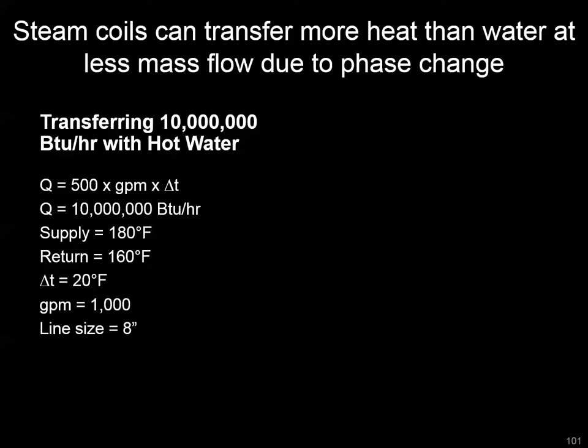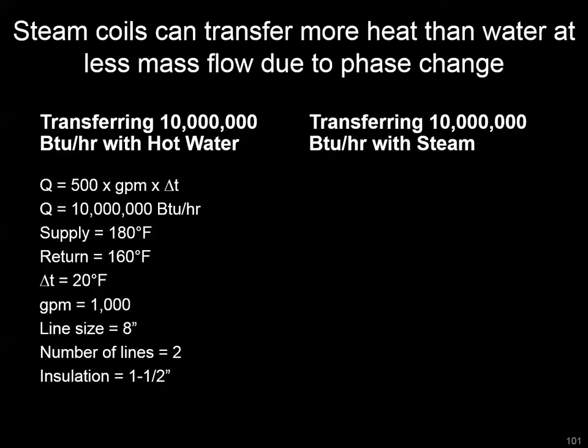For that hot water system we'd probably need an 8-inch supply line, plus a return, so two of those lines. ASHRAE would probably tell us to insulate at about an inch and a half. Comparing that with steam, we use a mass flow equation — we can't just look at delta T with a phase change, so we look at delta enthalpy and the pounds of steam moving across the system per hour.